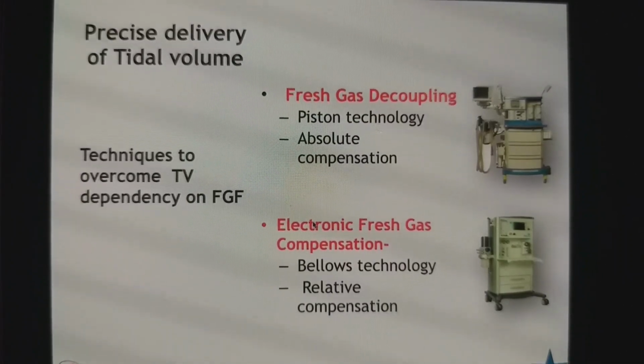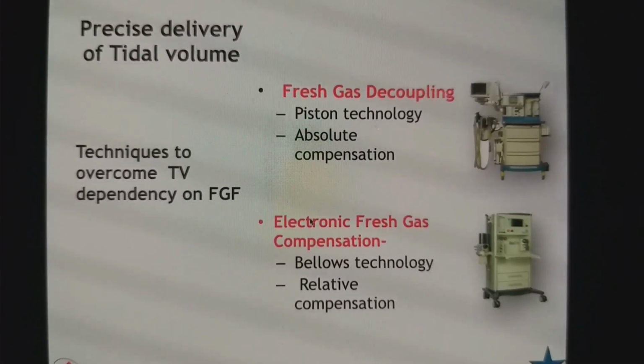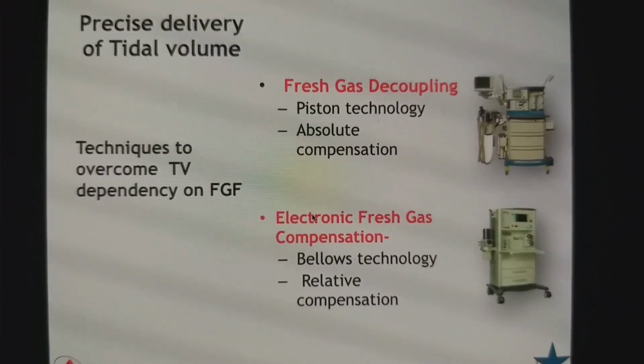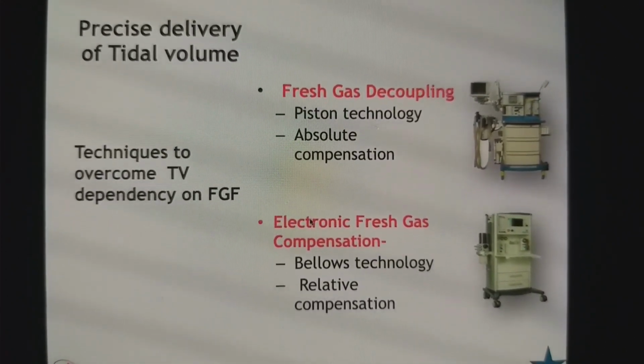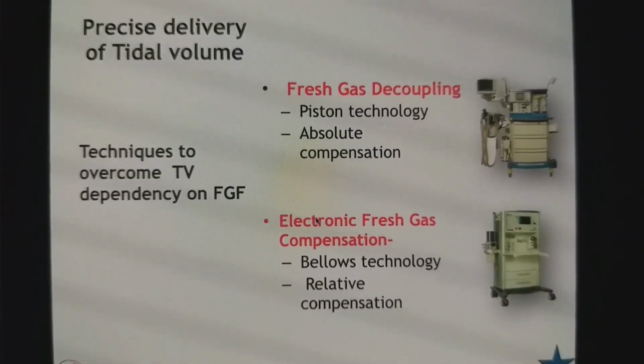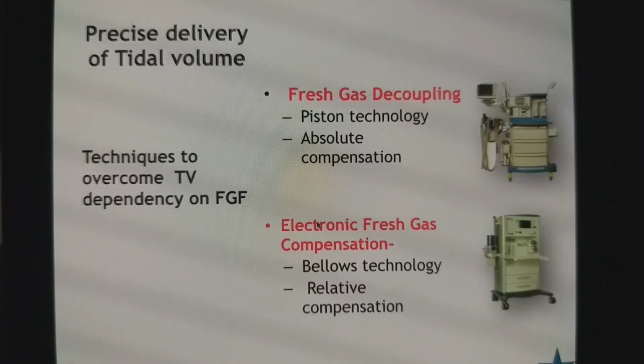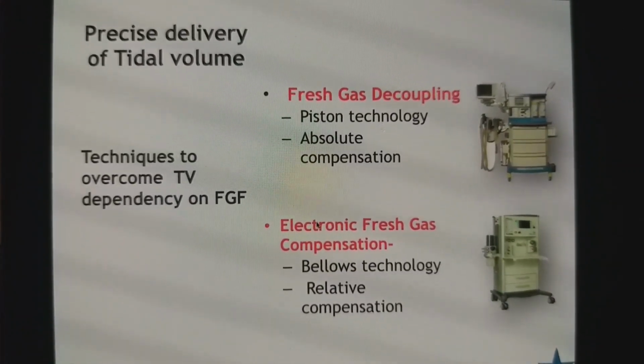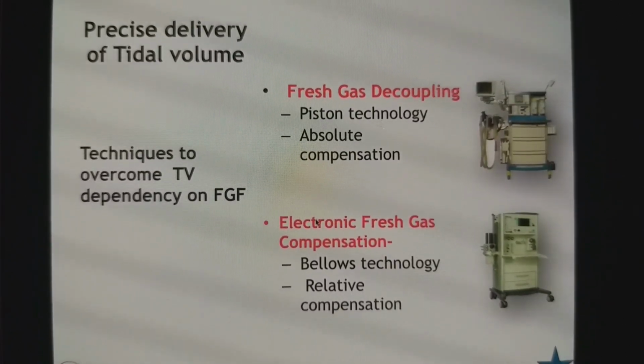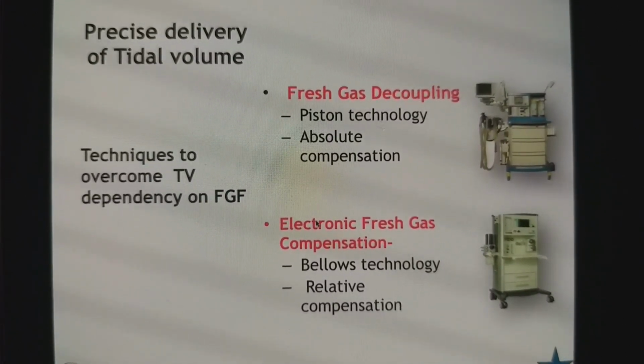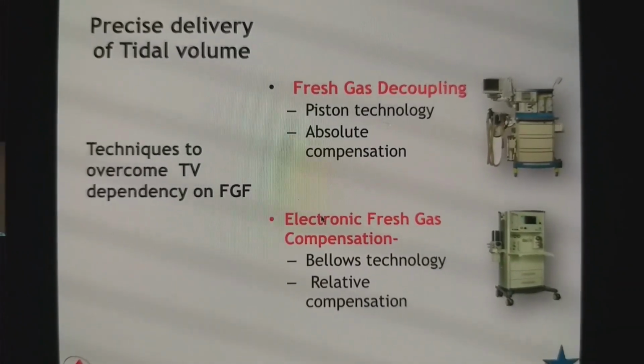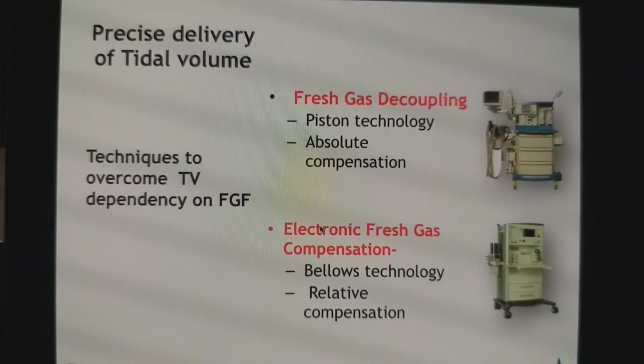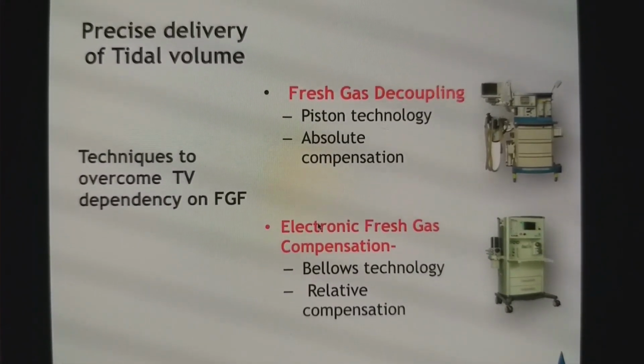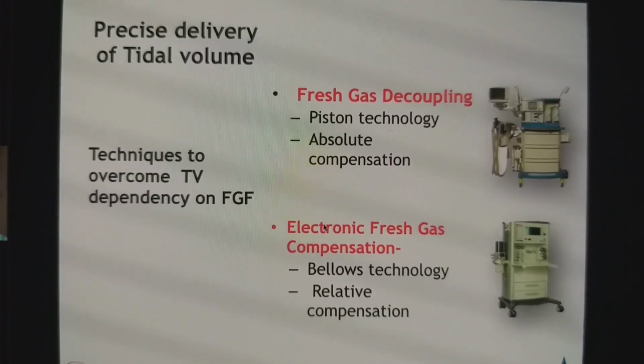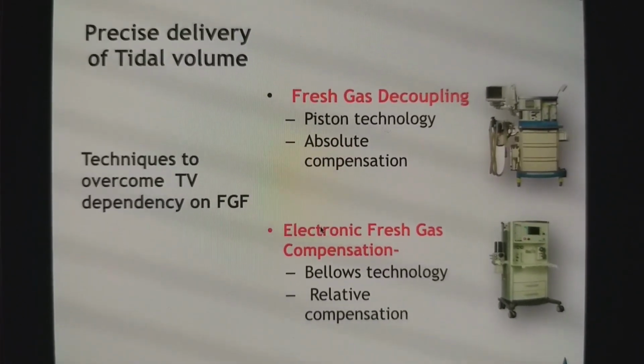While in the case of electronic fresh gas compensation, which is routinely there with all bellows technology, it is slightly relative compensation in many machines, because the message is given to the ventilator, and the ventilator will act in the next few breaths. So 1 breath, 2 breaths, or maybe up to 6 breaths it can take to compensate for the excess fresh gas flow. So it is a relative compensation. Though some new machines have sensors placed in the inspiratory line, and fresh gas flow is also digitalized, they will know a little earlier. But still, probably there will always be a breath where you have an extra amount of volume.